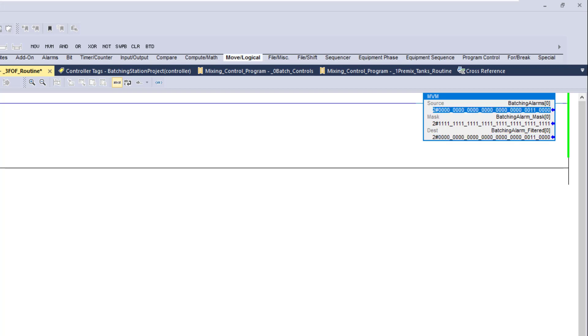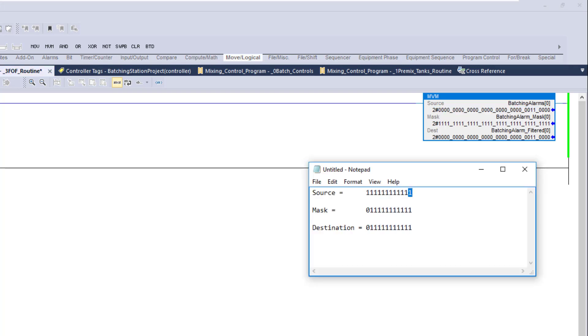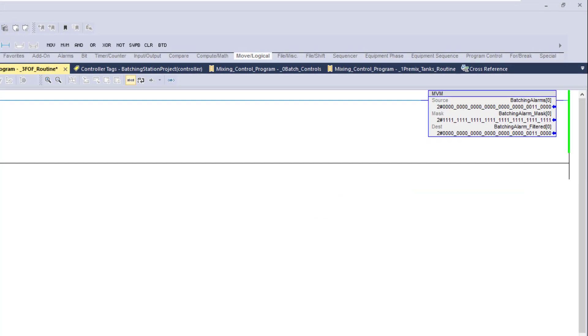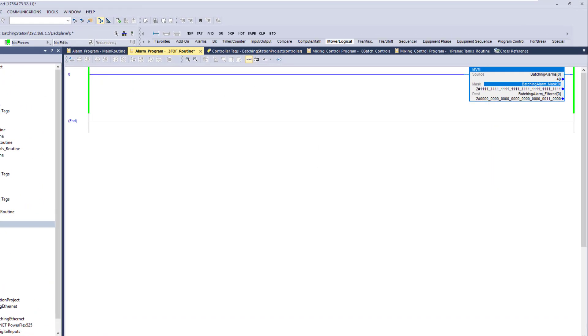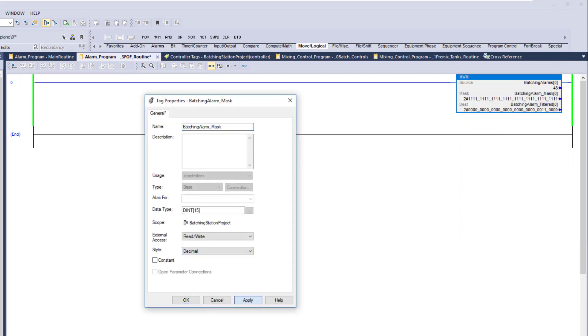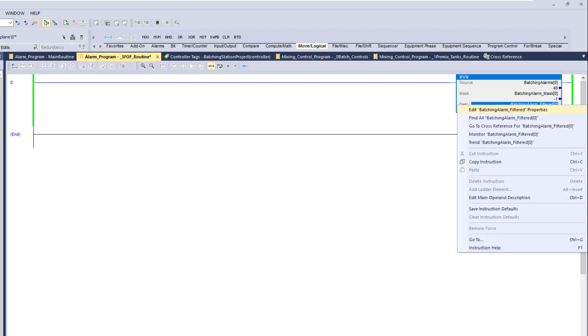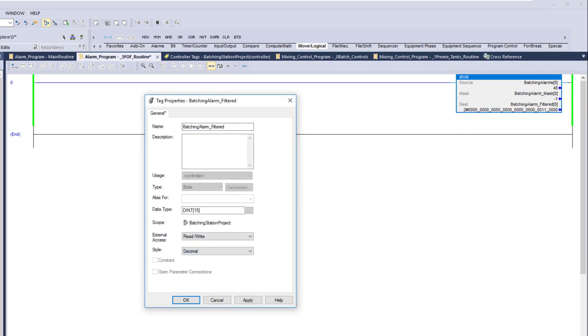That shows you how the mask move works. Simply put: it takes the binary form of the source, passes it through the binary enable/disable pattern of the mask, and allows the result to go to the destination. That is how a mask instruction works. I want you to have the foundational understanding of a mask before we go further. Now I'll change the display back to decimal form, which is the standard format you'll see 90% of the time.